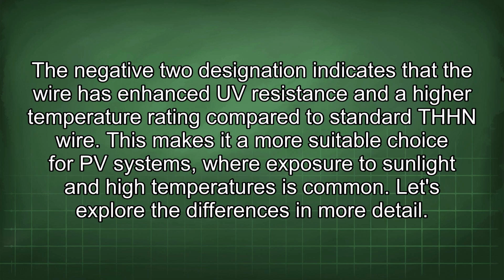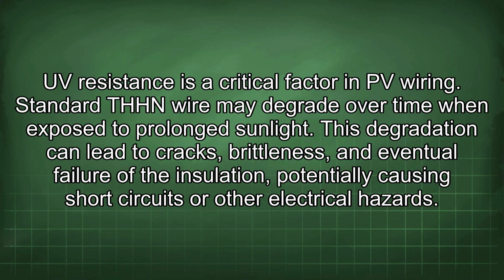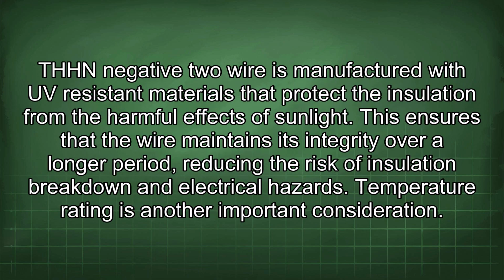Let's explore the differences in more detail. UV resistance is a critical factor in PV wiring. Standard THHN wire may degrade over time when exposed to prolonged sunlight. This degradation can lead to cracks, brittleness, and eventual failure of the insulation, potentially causing short circuits or other electrical hazards. THHN-2 wire is manufactured with UV-resistant materials that protect the insulation from the harmful effects of sunlight. This ensures that the wire maintains its integrity over a longer period, reducing the risk of insulation breakdown and electrical hazards.